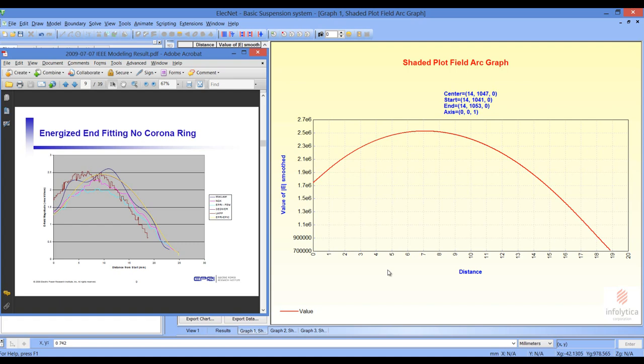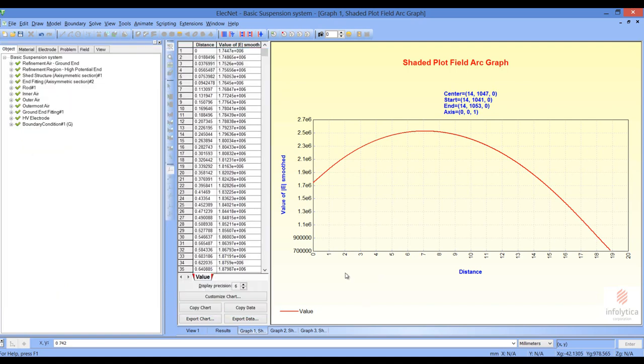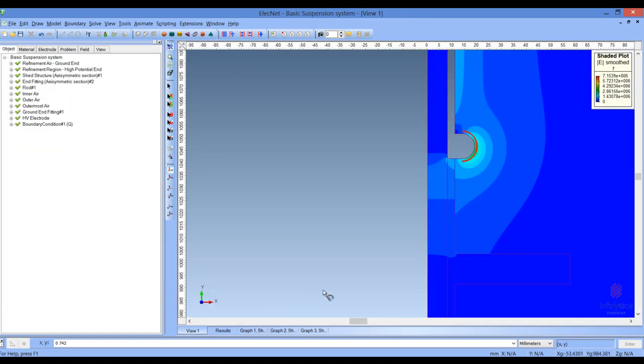Let's compare that to what we get in the EPRI document. Concentrating on the yellow curve in the EPRI document, you will see that the shape and values of the electric field stress are comparable, and the peak occurs approximately in the same location as in the EPRI document.